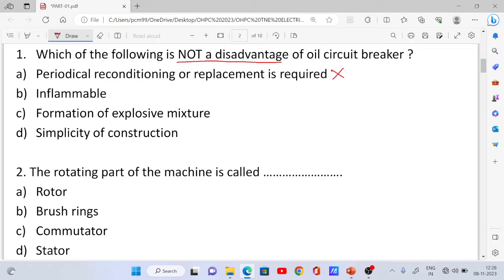Option B: Inflammable — the oil is flammable. Here, the oil circuit breaker uses oil which can ignite above 140 degrees Celsius, so this is a disadvantage. Option C: Formation of an explosive mixture when the oil degrades — this is also a disadvantage.